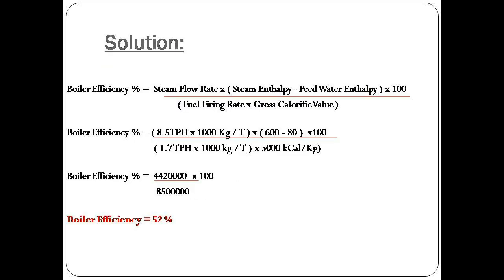Our formula is boiler efficiency equals steam flow rate multiplied by the difference of steam enthalpy and feed water enthalpy, divided by fuel firing rate multiplied by gross calorific value.